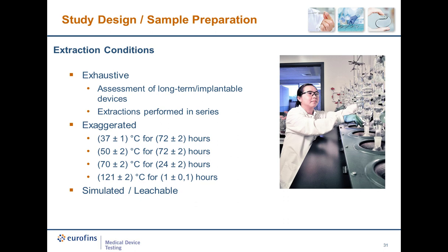The next consideration for the sponsor are the extraction conditions. The standard provides three different starting points for the extraction conditions: the clinical use of the device and its inherent risk to the patient determine which of the extraction conditions should be used. It is important to pick appropriate conditions to adequately assess the device without altering the device. Devices with long-term patient contact, like an implantable, should be evaluated using an exhaustive extraction. An exhaustive extraction is performed in series and is carried out until the last extraction is less than 10% gravimetrically of the initial extraction. This provides data to show that the extraction conditions have been rigorous enough to pull all potential extractables.